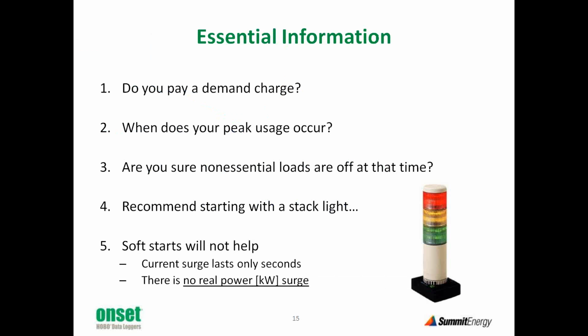So here's my recommendation. You should know if you pay a demand charge. Some of you don't, and so this isn't an opportunity. You should know when your peak occurs and make sure that you've only got essential things running. Now, there are PLC-based control systems that will monitor your usage, and as you approach a peak, start shutting things off. I've never seen that really practical for a couple of reasons. Most production managers are not going to take kindly to some controller that can start shutting things off. It just doesn't make sense. But also, if you start opening circuit breakers automatically, logically you're going to shut off things like the parking lot lights and other things like that, which probably aren't on during the peak period anyway.